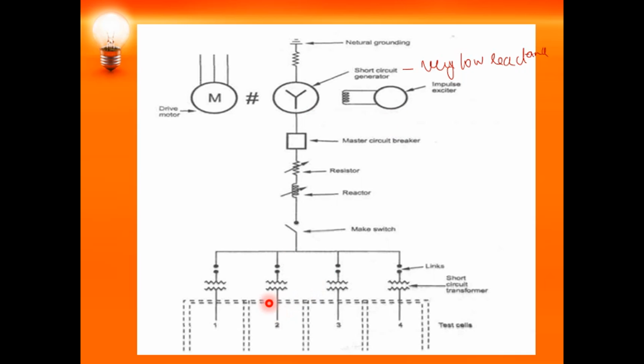Next, coming to the short circuit transformer. What is the short circuit transformer? The short circuit transformer again has a low reactance, and it is designed in such a way that it can withstand repeated short circuits. To get the different voltages for the test, its windings are arranged in sections. You can have either a series or parallel combination of these sections to get the desired test voltage. Why is the transformer required? A transformer usually steps up or steps down, right? To get a lower voltage than the generated voltage, to apply to the circuit breaker under test, you have a short circuit transformer.